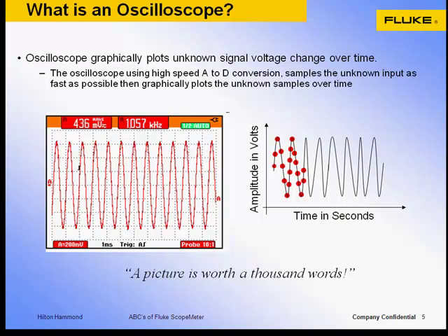The advantage of this technique is the conversion speed. The disadvantage is in the resolution, and thereby overall measurement accuracy. The scope's vertical accuracy is around 1.5%, compared to a basic 3.5-digit multimeter being less than 0.15%.